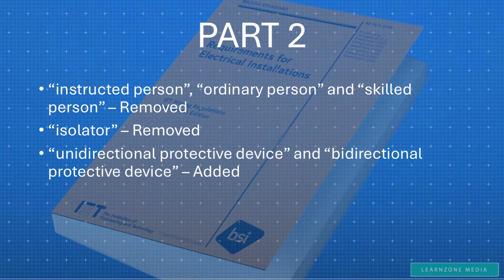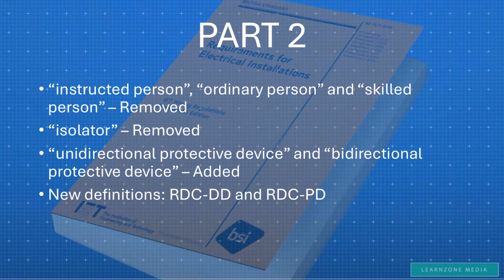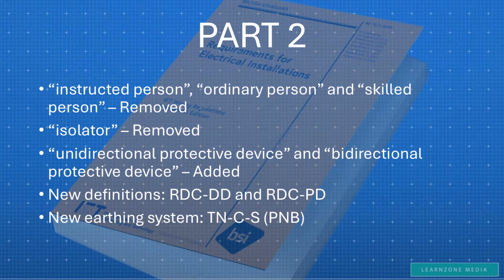Special attention to the terms unidirectional protective device and bidirectional protective device, which are now used for devices such as RCDs. New definitions: residual direct current detecting device, RDCDD, and residual direct current protective device, RDCPD. And the big one, the new TNCS PNB system, which is actually nothing new, but it's new for the regulations - so, new but not new. We'll talk about this a bit later.